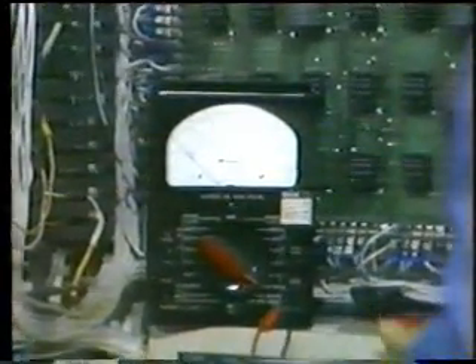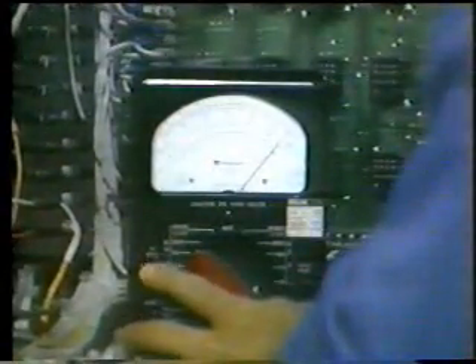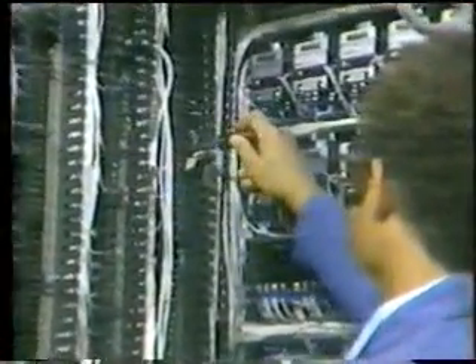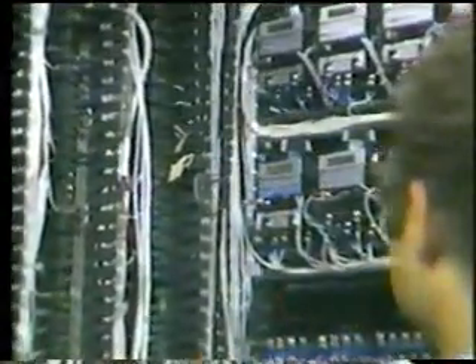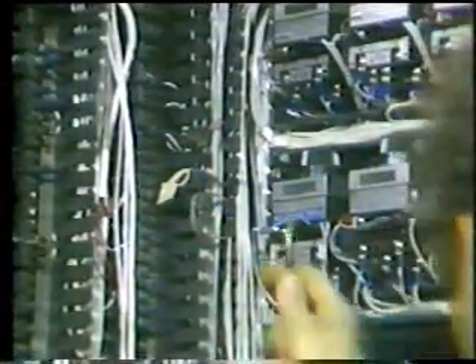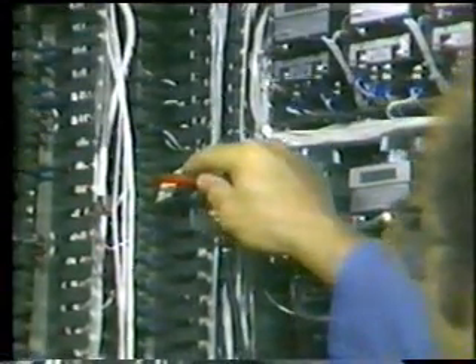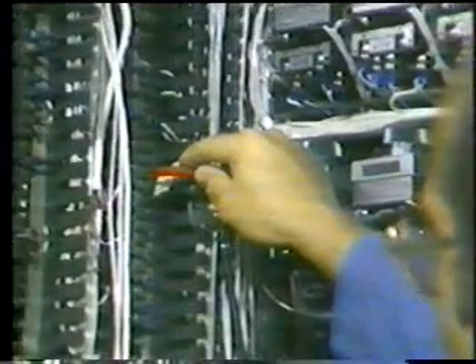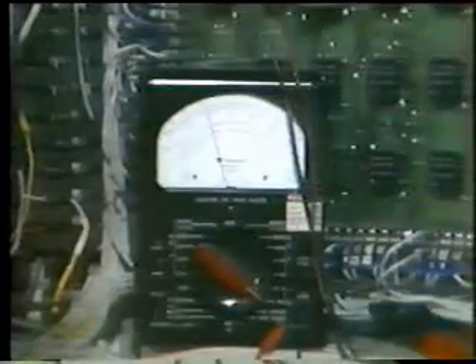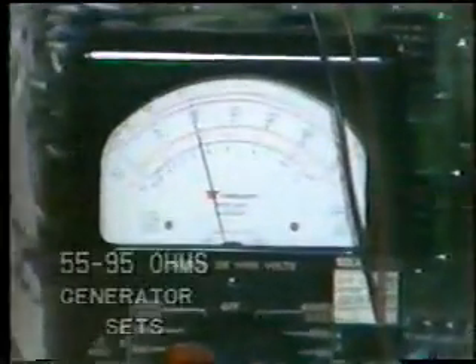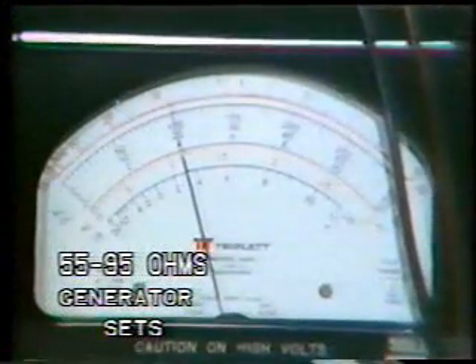Begin by zeroing the meter on the R times 10 scale. Next, remove one of the wires at the terminal that leads directly to the magnetic pickup. Connect one of the meter leads to the loose wire and the second lead to the pickup wire at the terminal strip. Be sure that you connected the meter to the wires that lead directly to the magnetic pickup and not through the solid state device. Check the reading on the multimeter. It should be 55 to 95 ohms.